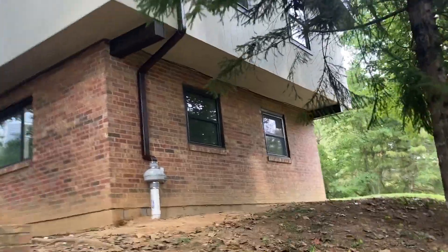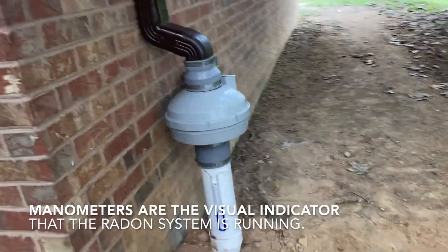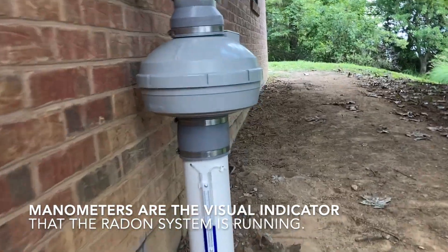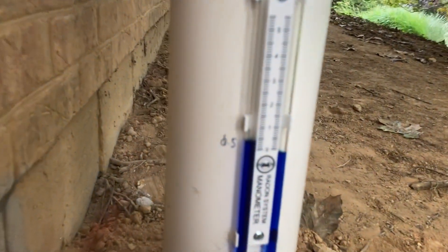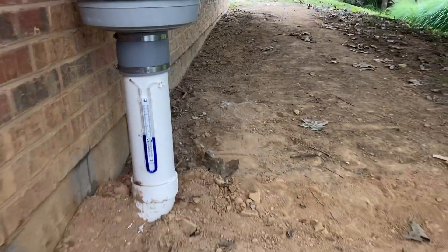You'll notice the manometer. Systems need a manometer and since there's nothing inside the house, this is how we went about attaching it — and this is my little trick to keep water out of the manometer. We went ahead and wrote down the vacuum number there, because those little stickers that come with the manometer kits don't stick so well after a little while outside.